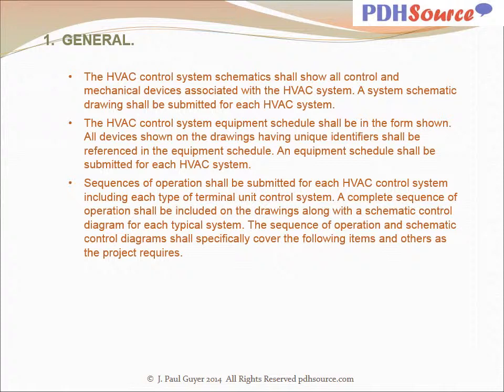Sequences of operations shall be submitted for each HVAC control system, including each type of terminal unit control system. A complete sequence of operations shall be included on the drawings along with a schematic control diagram for each typical system. The sequence of operation and schematic control diagram shall specifically cover the following items and others as the project requires.